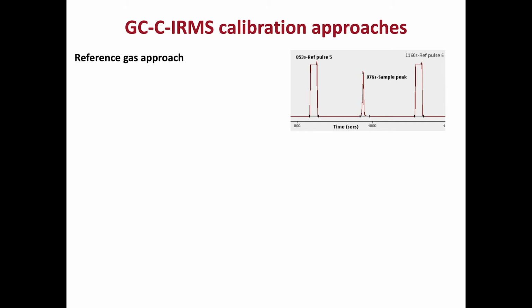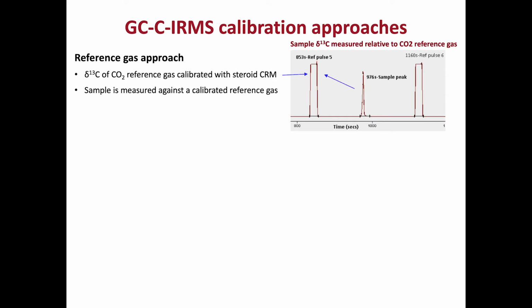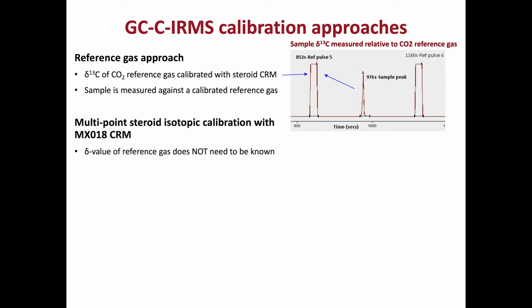The current routine approach to GC-C-IRMS calibration is the reference gas approach, where the internal CO2 reference gas has to be calibrated by a steroid CRM prior to sample measurement. The unknown sample is then measured against the reference gas. The multi-point steroid isotopic calibration is a new approach NMIA has adopted since the release of the MX18 CRM.